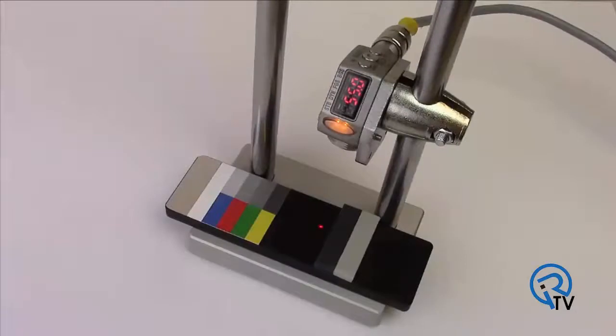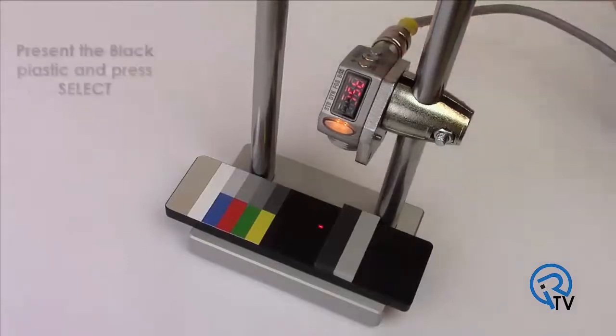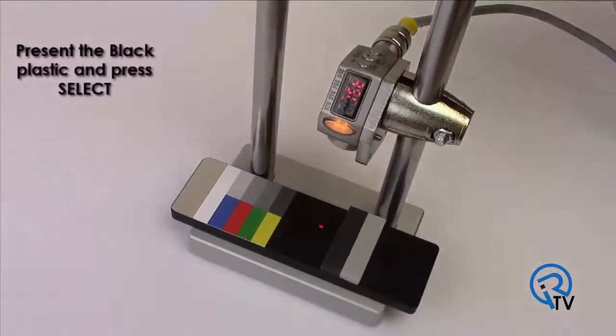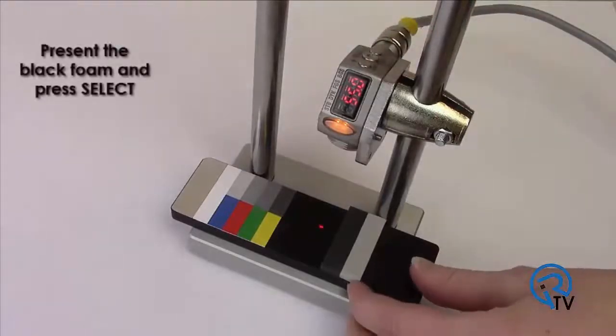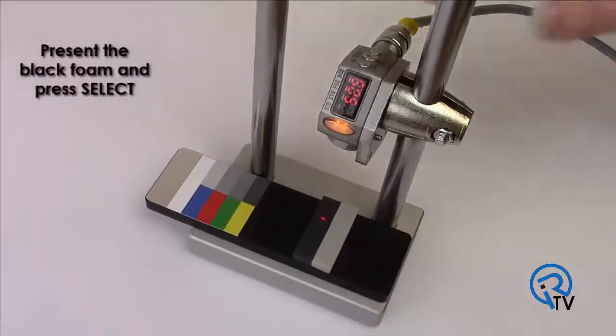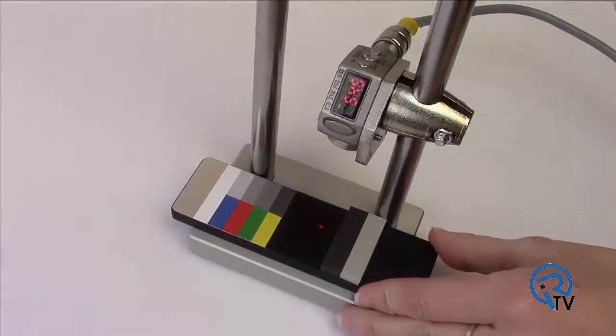The display shows the current distance. Press and hold teach for two or more seconds. Present the black plastic piece and press select. Now present the black foam and press select. The display flashes and returns to run mode. The foam is now detected but not the background.